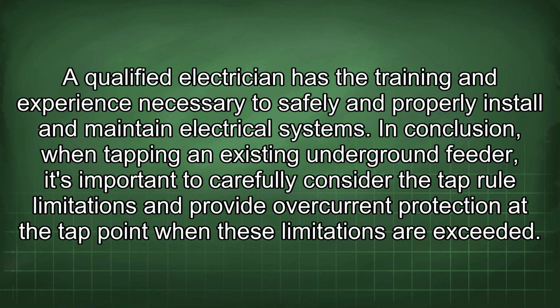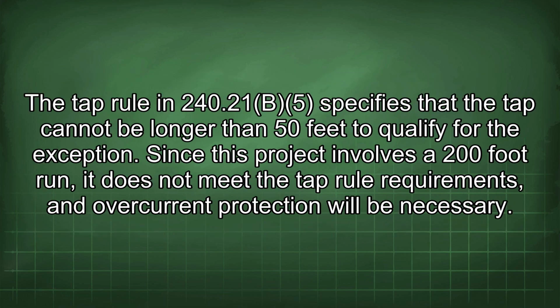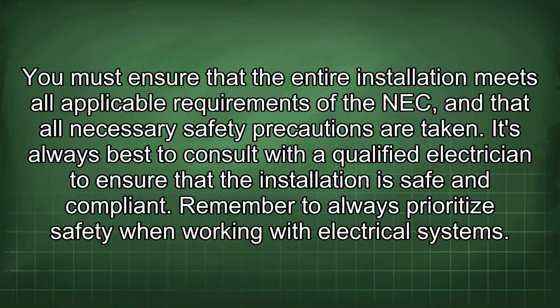In conclusion, when tapping an existing underground feeder, it's important to carefully consider the tap rule limitations and provide overcurrent protection at the tap point when these limitations are exceeded. The tap rule in 240.21(B)(5) specifies that the tap cannot be longer than 50 feet to qualify for the exception. Since this project involves a 200-foot run, it does not meet the tap rule requirements, and overcurrent protection will be necessary. You must ensure that the entire installation meets all applicable requirements of the NEC and that all necessary safety precautions are taken. It's always best to consult with a qualified electrician to ensure that the installation is safe and compliant.